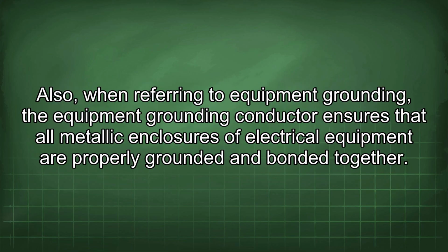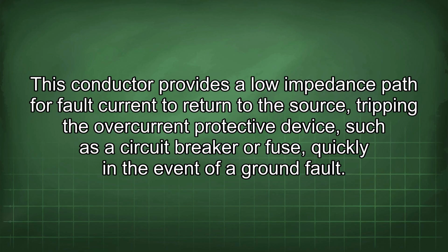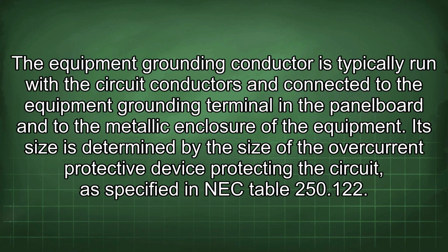Also, when referring to equipment grounding, the equipment grounding conductor ensures that all metallic enclosures of electrical equipment are properly grounded and bonded together. This conductor provides a low impedance path for fault current to return to the source, tripping the overcurrent protective device, such as the circuit breaker or fuse, quickly in the event of a ground fault. The equipment grounding conductor is typically run with the circuit conductors and connected to the equipment grounding terminal in the panel board and to the metallic enclosure of the equipment.